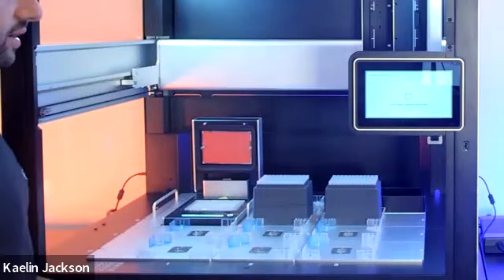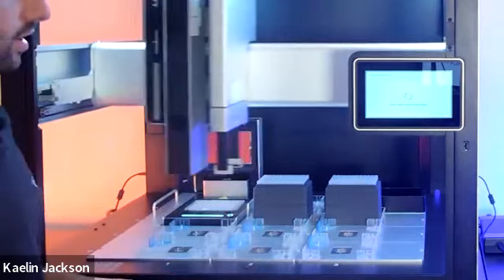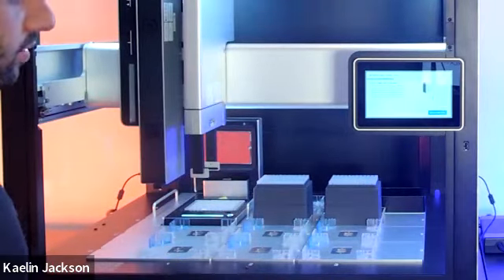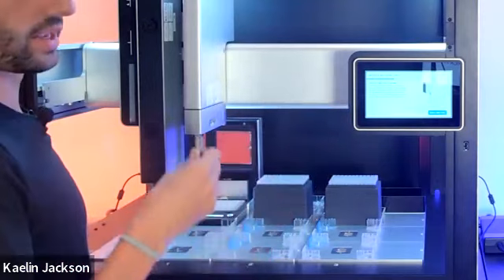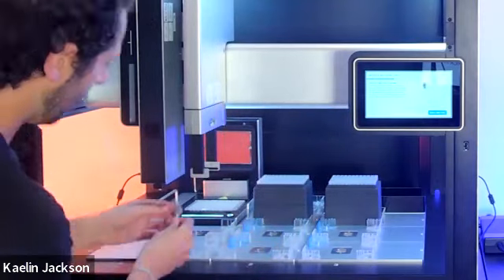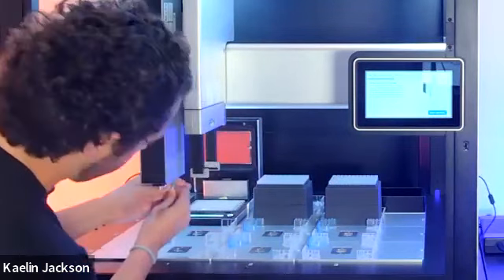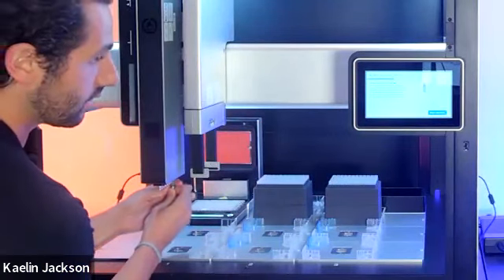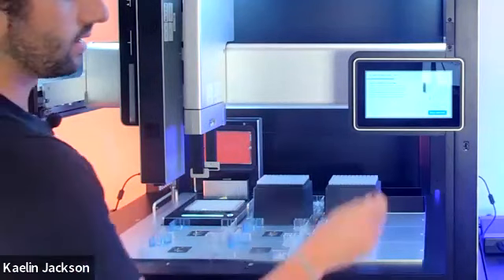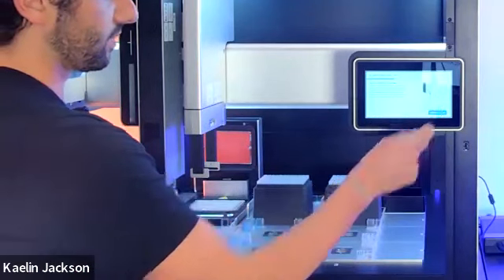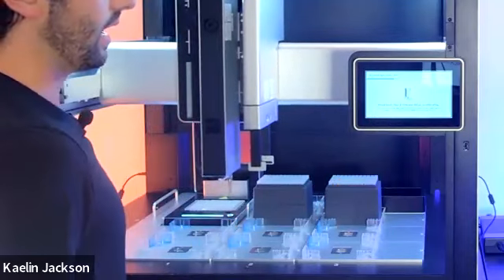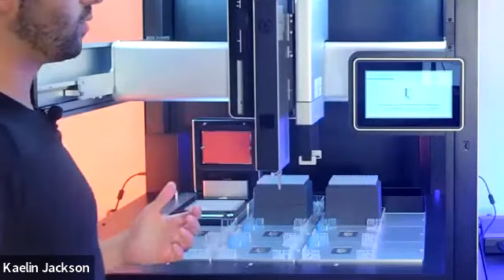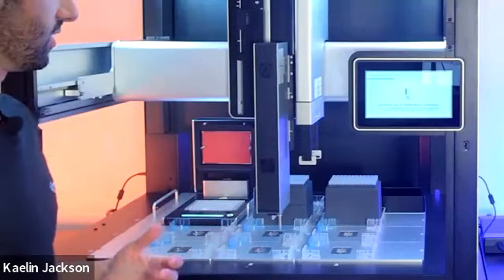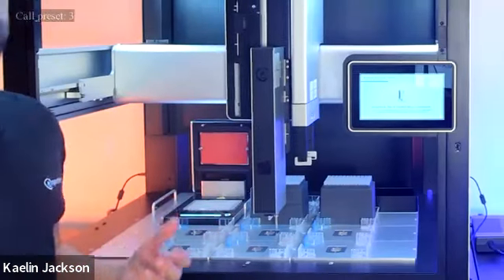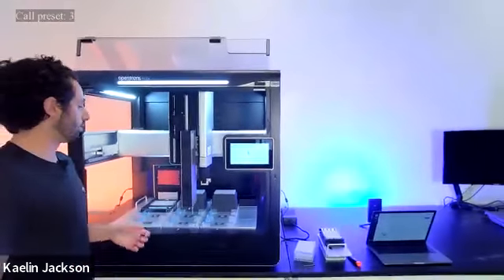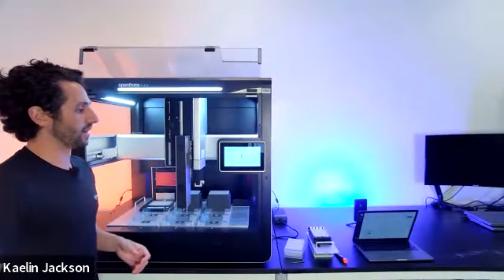I'll move the pipette to the front, again, ensuring that slots 2 and 5 are not occupied. And here there's a modal letting me know exactly what I need to do with the calibration probe. I'll place it on the backmost channel of our pipette, screw it in by hand, make sure it's tight, and select begin calibration. And with that, we can walk away knowing that the robot will access its capacitive sensing technology to align itself in the X, Y, and Z axes with up to 0.1 millimeter resolution to make sure our pipette is really finely accurate.